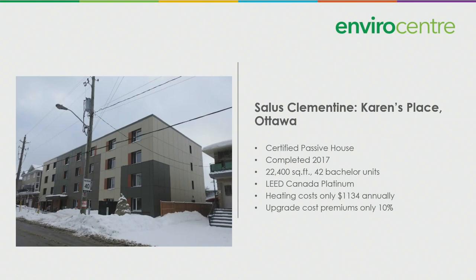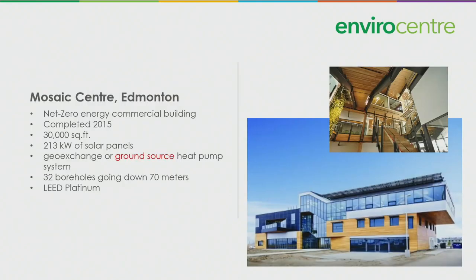that size would use. Here's the Mosaic Center in Edmonton. It's a net zero energy commercial building. So it was this and the previous building were built from scratch. It was completed in 2015. It has a ground source heat pump system or a geo exchange system, which is 32 boreholes going down 70 meters. That's located under the parking lot. And it's also rated LEED Platinum. It has 213 kilowatts of solar panels up there on the roof.